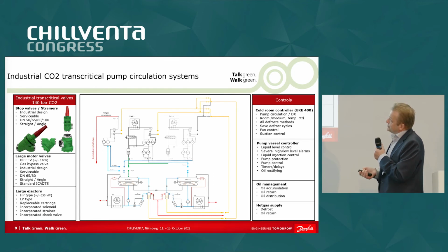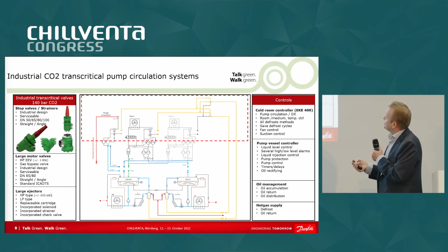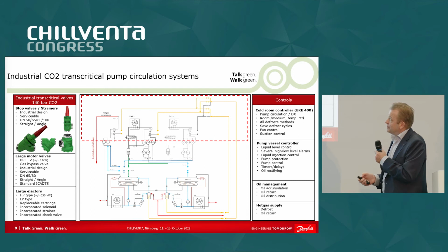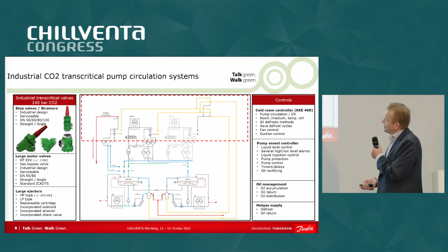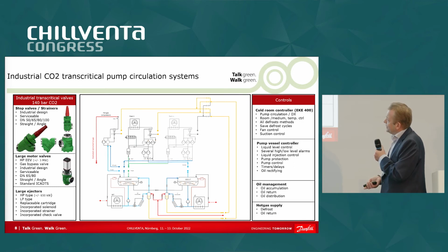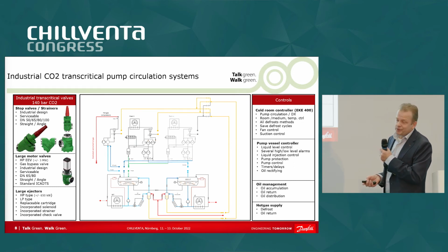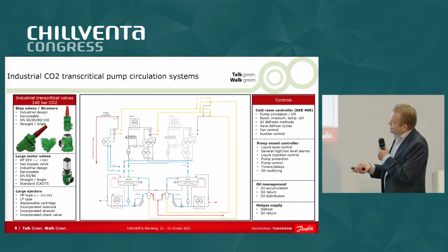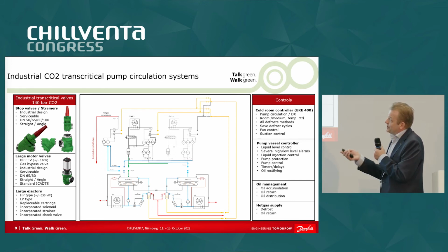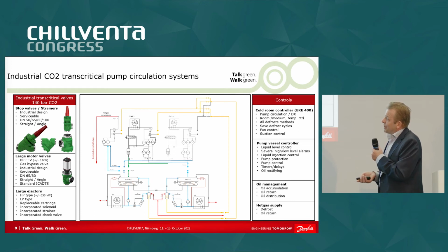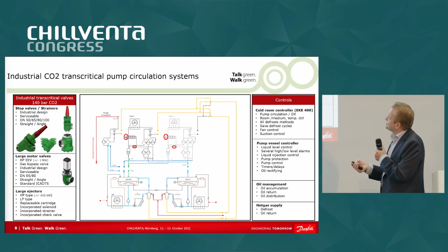So we have launched a series of stop valves and filters, size 50, 65, 80, and 100, to be sure that we can cover this part of the system. So now we can offer these valves for racks, for OEM racks, to support these larger capacities. That's one. Then we need much larger high pressure expansion valves. So these are motor valves. We have the ICMTS 20, maybe you know. It's a relatively small one for commercial, but now we need a bigger one. So now we are working on large motor valves, and they are placed here as high pressure expansion valves, this one, or we can use them as gas bypass valves.